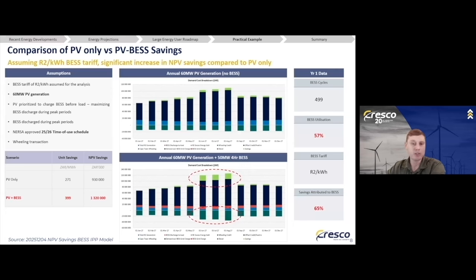And then the largest increase occurs in the winter high season months, June, July, and August, because this is where peak tariffs and Eskom retail tariff plan exposure is the highest. But what's interesting in this case is that around 65% of the NPV of savings is attributed to the BESS, even though it only cycles about 500 times a year and it's utilized at roughly 57%.